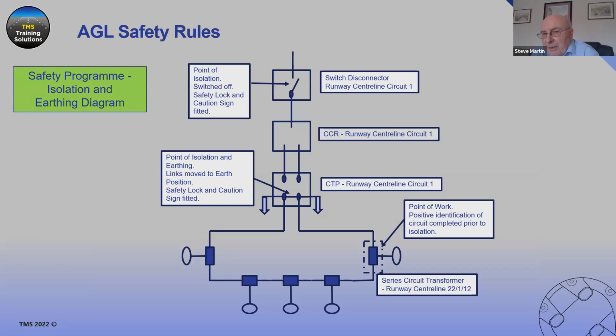We've positively identified it beforehand. We've got the circuit isolated at the output disconnecting device, CTP as it's mentioned here, and we've moved the links to the earth position, and we'll have had that locked with a safety lock and a caution sign. At the top, the incoming LV supply has also been isolated and locked off as well.